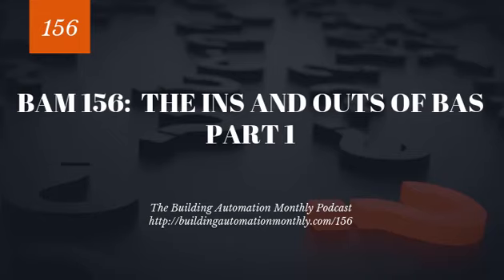However, I will also tell you that there are manufacturers out there, especially with BACnet devices, who create analog inputs and binary outputs and binary inputs and analog outputs that have no tie to an actual physical point. That's a big no-no. That's breaking kind of the standard for BACnet, but hey, that's what some people do. So do not always equate a software input with an actual physical point. So that's my point there.